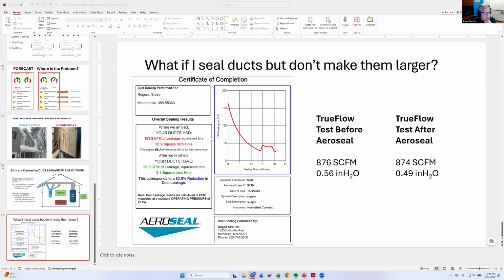I did an AeroSeal on the duct system in my 1958 house, and this is the report saying that when they started, the duct leakage was 164 CFM, and when they finished, it was 28.5. You can see on the report that I had about a 30.9 square inch hole to begin with, and it was down to a 5.4 square inch hole of leakage when they finished. I also did a TrueFlow test before and after the AeroSeal. Before, I was measuring 876 CFM at a static pressure of 0.56. After, I was measuring 874 at a static pressure of 0.49. Those are not reversed. But I think there may have been a slight mistake here in that possibly in the after test I had my humidifier bypass open and maybe it was closed in the initial test.